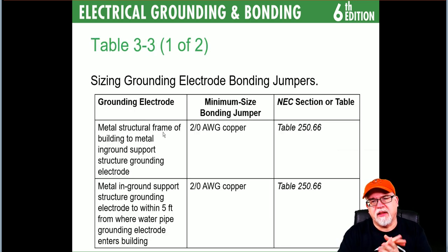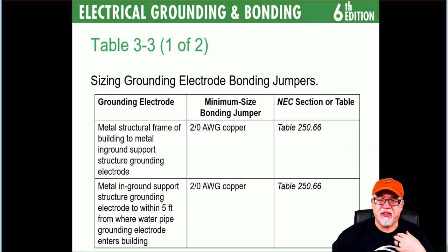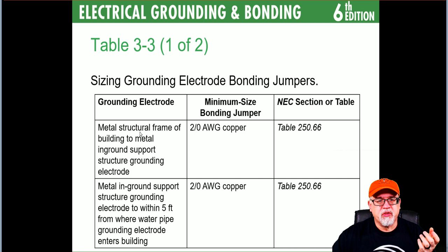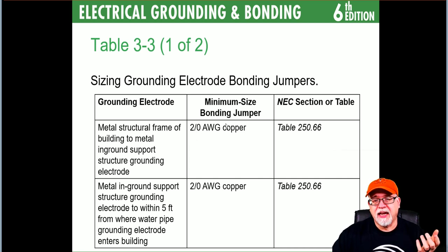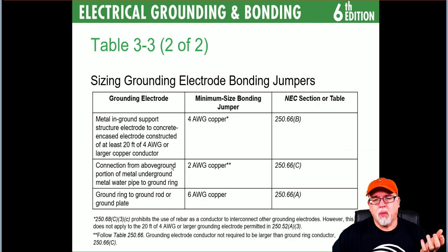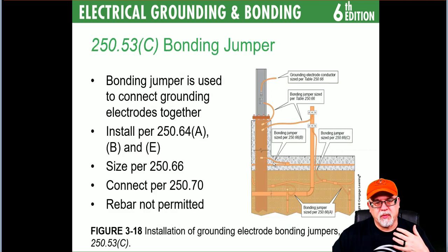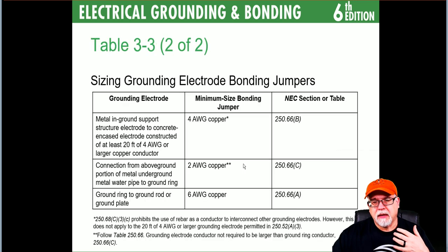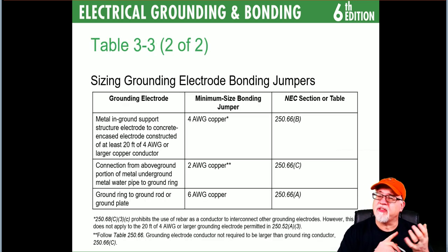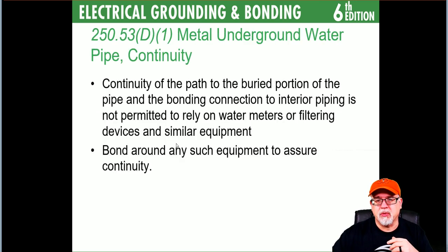For sizing the electrode bonding jumpers: if it's structural framing or building metal in-ground supports, the minimum size bonding jumper is 2/0 AWG copper per Table 250.66. In the program we will walk you through every sizing requirement. For electrodes not covered by 250.66(A), (B), or (C) — such as rod, pipe, plate, concrete encased electrode, and ground rings — you simply pull from the table and size accordingly.